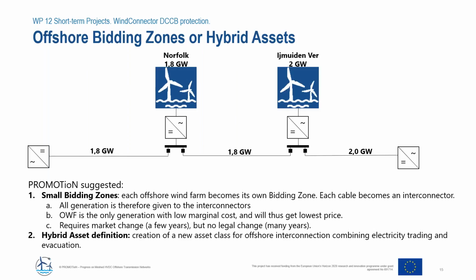According to European law, there is an obligation to make at least 70% of cross-border interconnection capacity available for trade. For WindConnector, this cannot be achieved when generation of the Dutch wind farm is above around 700 megawatts, or generation of the UK wind farm is above around 500 megawatts. For better understanding, the total capacity of these farms is just twice those numbers. So basically, whenever generation is above 40 or 50%, this goes against European law.